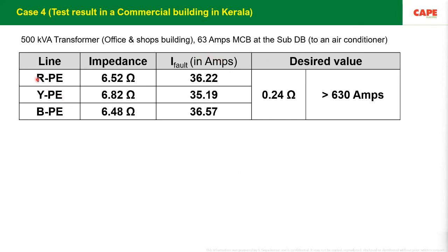The result which I got is R to P, R phase to earth impedance is 6.52, the fault current is 36 amps, and you can see here the average earth fault current in that MCB was about 35 to 36 amps. Whereas this MCB requires 630 amps to trip within the specified time. So the earth fault current which is actually flowing is not even, you can see here, 5% of what is necessary. The current is very, very small.